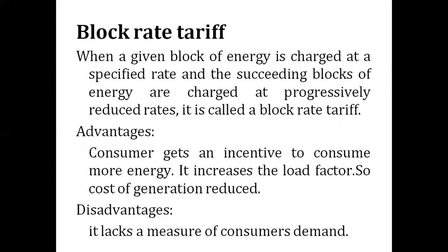So in order to overcome this, another concept was formed, called the block rate tariff. In the block rate tariff, a given block of energy is charged at a specified rate, and the successive blocks of energy are charged at progressively reduced rates. It means a block of energy is charged at some rate, say rate A, and after that it is progressively reduced. This is generally known as the block rate tariff concept.